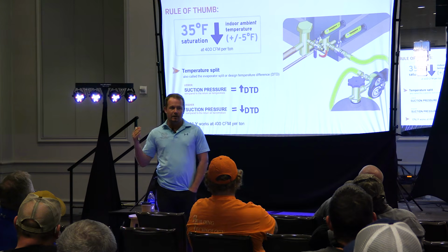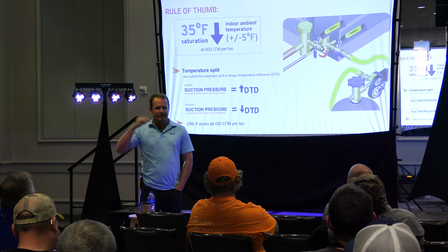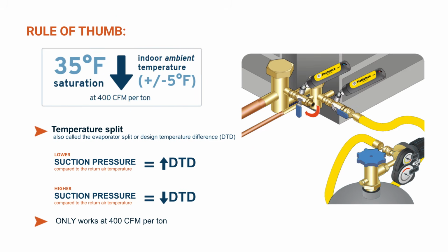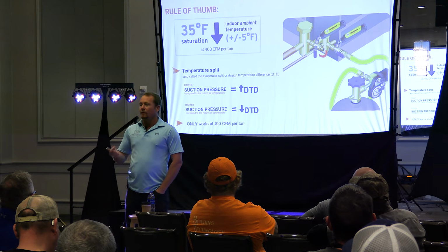And it doesn't really matter much. Even outdoor temperature, condensing temperature, that doesn't really drive it too much. It's really just the energy in that air driving that boiling temperature, creating an equilibrium at around 35-degree TD, around there. We'll say between 30 and 35. And so from a heuristic standpoint, that's something that everybody can understand. It doesn't need to be a lot more complicated than that.